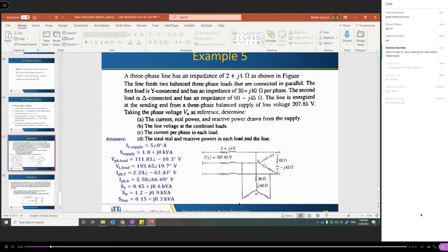So most loads are not represented by their impedances. It is actually very hard to calculate the impedance of loads, because the impedance is time varying. It depends on the operating condition, the temperature, the time of day, many factors, maybe the speed of the motor.